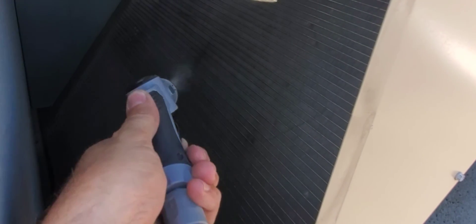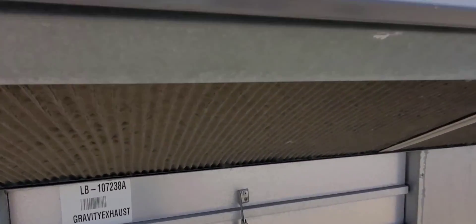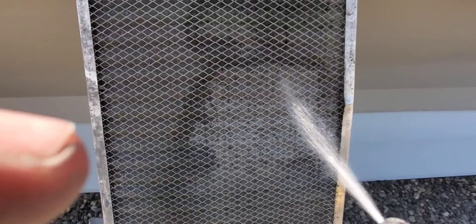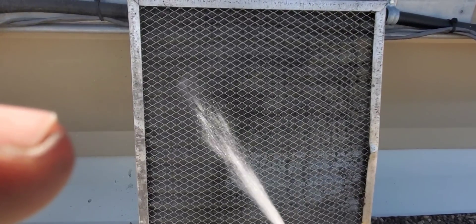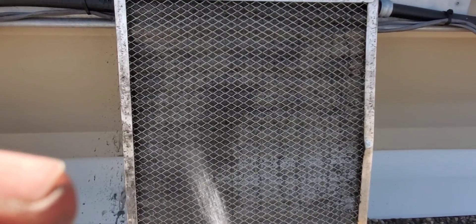The coil cleaner is really doing the trick and it doesn't feel like we've lost any pressure, battery power, or anything like that. Once we're done, we're also going to give the fresh air intake screens a good cleaning, because this unit runs in economizer mode when it's cold enough outside and those screens plug up fast. Look at that dirt.